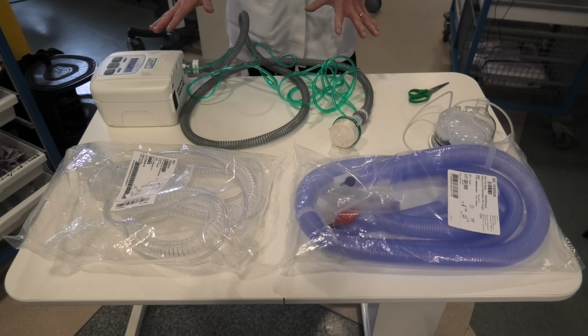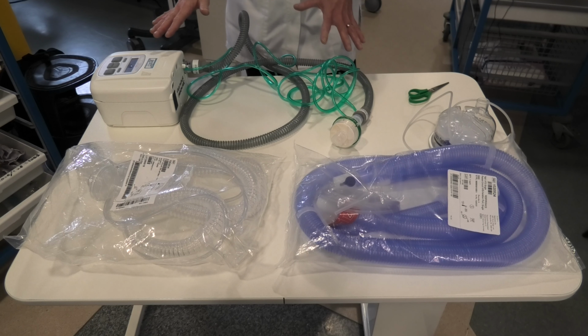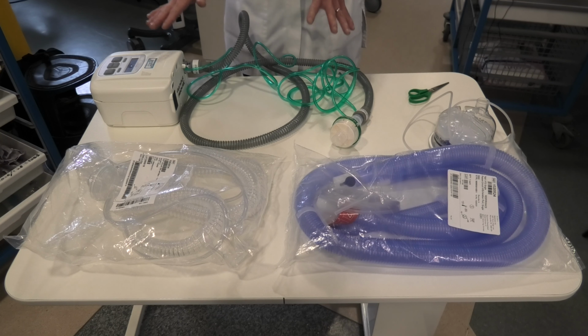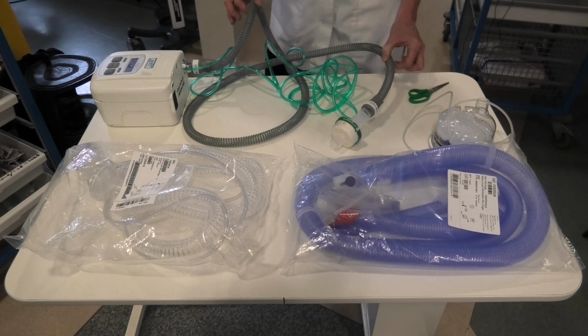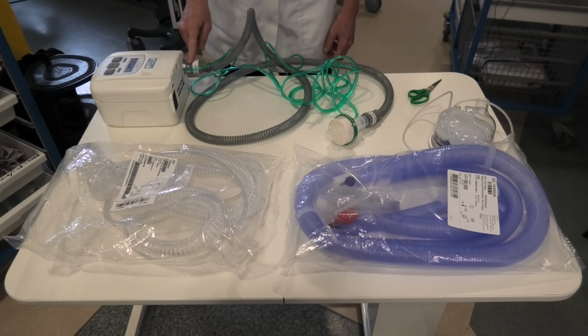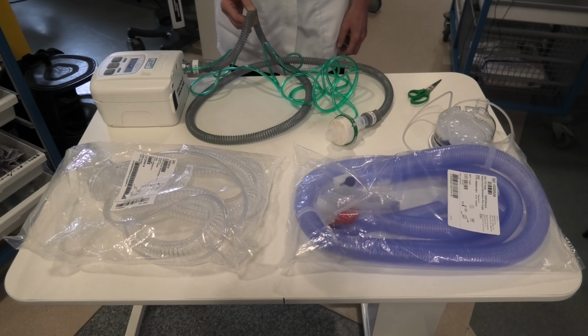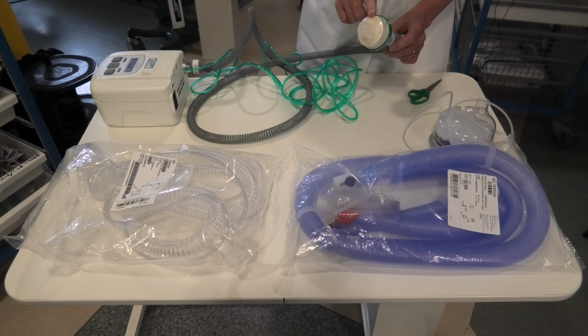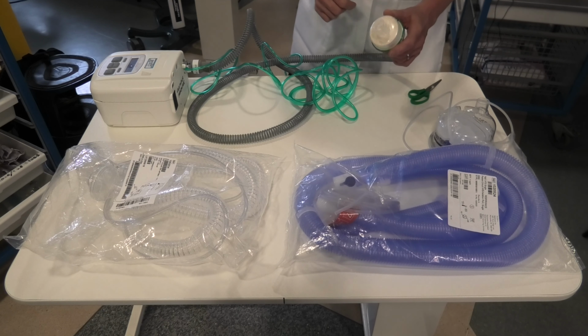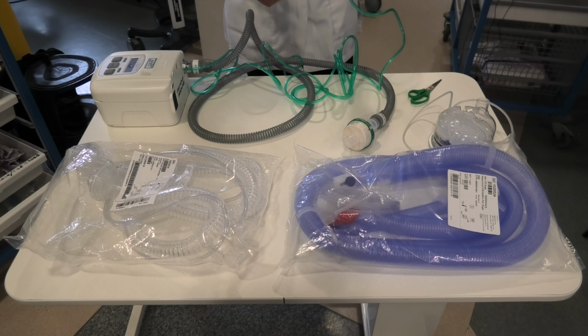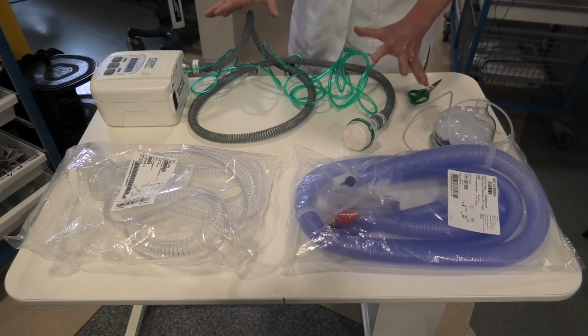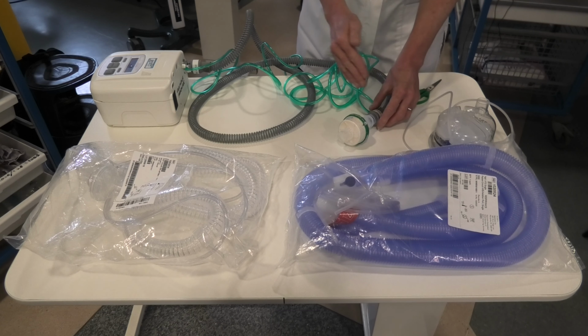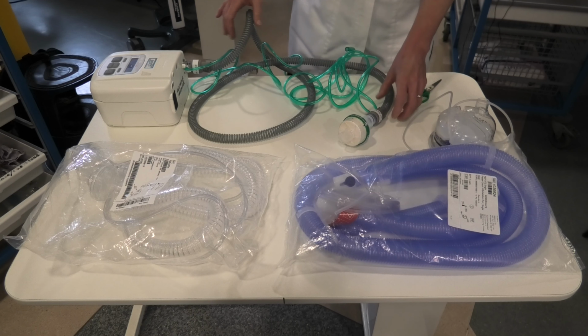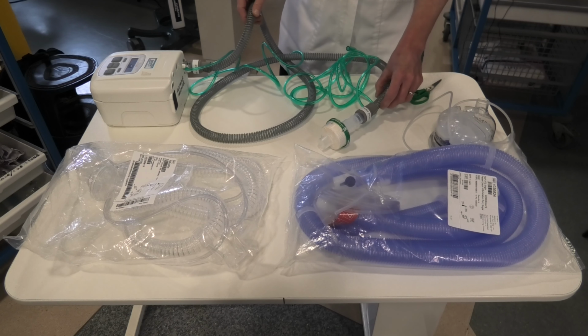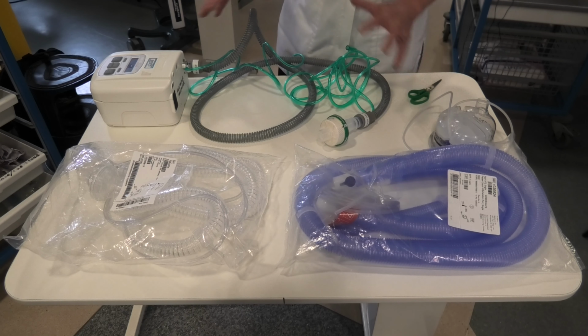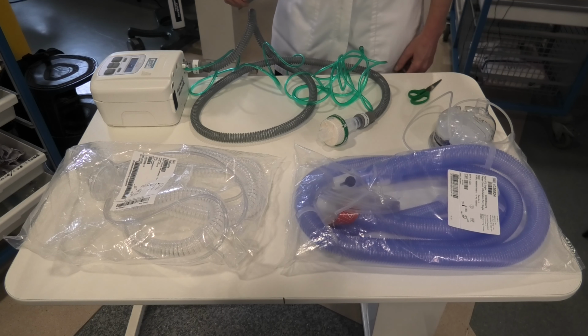Here we've got a sleep cube, which we used during the COVID-19 crisis, and we are still using them. Essentially, it's a fixed CPAP that comes with its own circuit. We have an oxygen entrainment port at the bottom, again, non-collapsible tubing. We have a filter at the patient end, and we fit the mask onto there. The oxygen tubing goes onto the flow meter on the wall. We like that these circuits are filtered at the patient end, so inhaled and exhaled gas is filtered, and we can reuse this circuit. So once this circuit has been used, it needs to be retained, and we clean it and we use it again for the next patient.